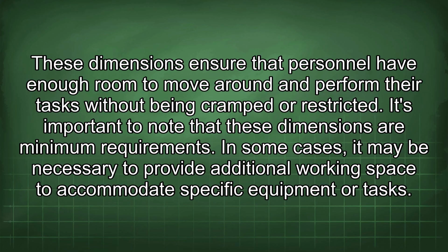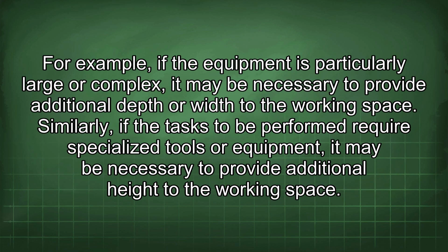It's important to note that these dimensions are minimum requirements. In some cases, it may be necessary to provide additional working space to accommodate specific equipment or tasks. For example, if the equipment is particularly large or complex, it may be necessary to provide additional depth or width to the working space. Similarly, if the tasks to be performed require specialized tools or equipment, it may be necessary to provide additional height to the working space.